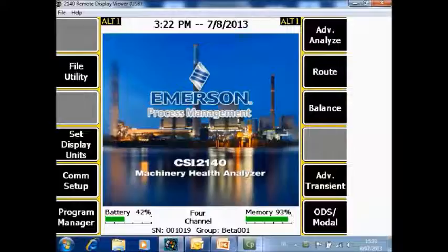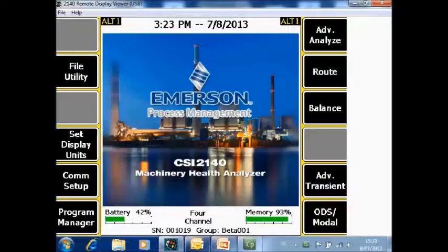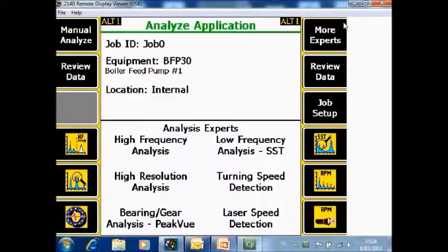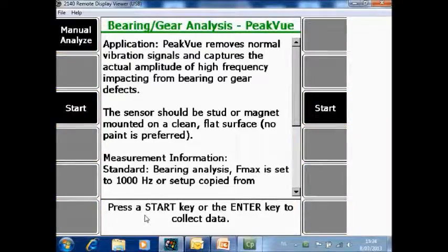PeakVue measurements can also be collected in the job mode. What you are seeing now is once again the home screen of the CSI 2140 Machinery Health Analyzer. Go to F7 analyze, then go to F6 bearing gear analysis PeakVue, and start data collection.